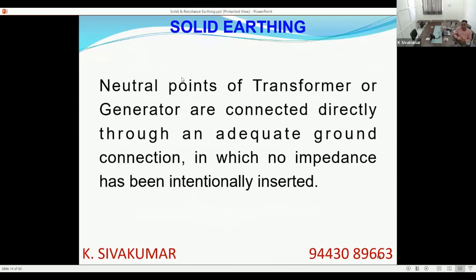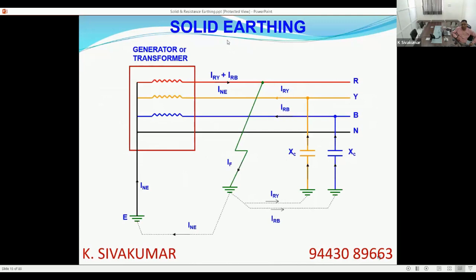Now, in layman's language, what is solid earthing? The neutral point of a transformer or generator is connected directly through an adequate ground connection. Adequate in the sense of sizing, thermal sizing, dynamic sizing, all those things, in which no impedance has been intentionally inserted. We do not add any resistance, we do not add any reactance in the neutral to ground path. So it is as direct as possible. A solid conductor is connected between neutral and earth, like this in this figure. You can see in the neutral to ground path, the black colour bus bar is the neutral bar, and to earth there is no resistance or reactance added intentionally.